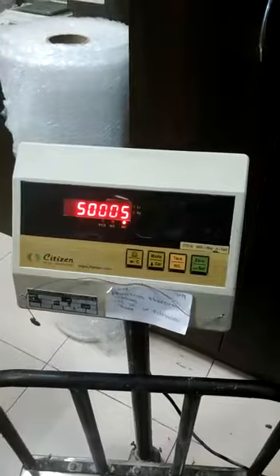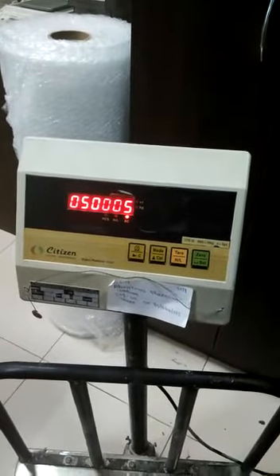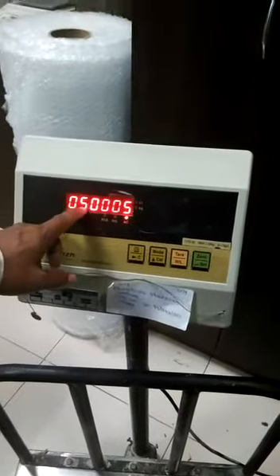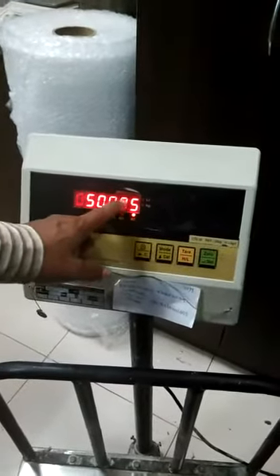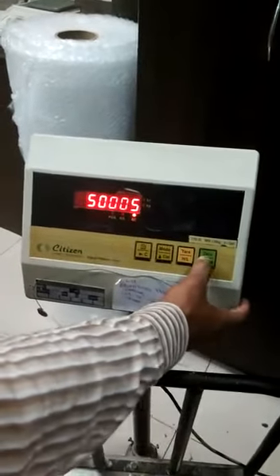You have to set the capacity, whatever the scale is. If you have a one-ton scale, you have to put 1000, then 0, 0, 1, 0 for the accuracy of the balance, then press enter.